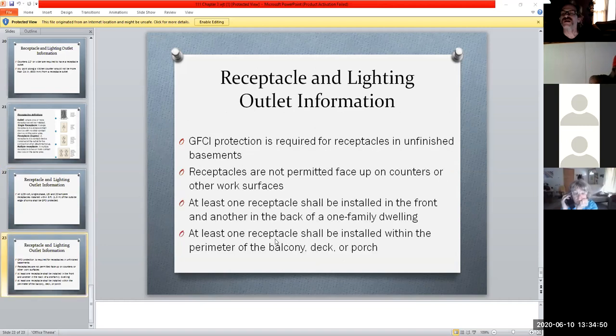But that's really the main gist of chapter 3 here: we get introductions to how we size, considering what our mandatories are, how we size the circuitry, and what formulas we're going to use. And usually, like I say, we're not going to get really complicated. Your general rule of thumb with the lighting branch circuits is 3 VA as our multiplier for that. And then we go through, and like I say, a lot of times you'd be able to look up values within charts.